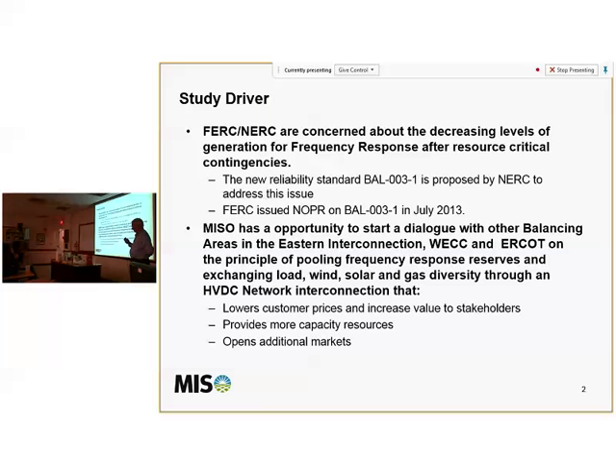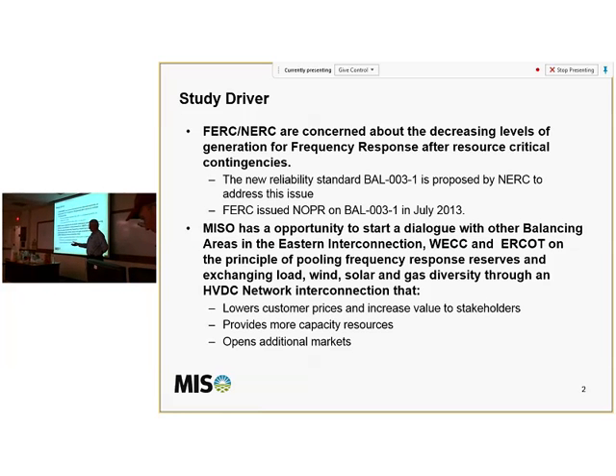I started about a year ago working on a subject. NERC and FERC were getting upset about frequency response. In the past, the way frequency response worked, everybody put a little extra reserve on their generator and carried higher pressure and higher temperatures in boilers. So you had some stored energy in the system. Then if you lost one big generator, you could call from that energy base to bring the frequency back to normal. I suppose some of you didn't know we stored energy in the electrical system in boilers, but we do.